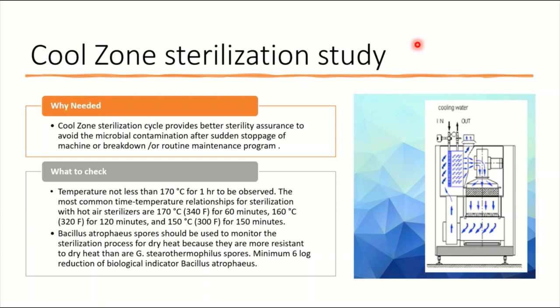This study came out in the last few years, called cool zone sterilization. Here, a couple of temperature combinations: 170 degrees Celsius for one hour to be observed. There are lots of combinations like 160 degrees for 120 minutes, 150 degrees for 150 minutes. Lots of combinations people are trying based on process design and development. The intent is that we need to demonstrate six log reduction by using biological indicator like Bacillus atrophaeus. Bacillus stearothermophilus is not the BI of choice for dry heat. You need to demonstrate six log reduction. That is the expectation of the cool zone. I have an article on cool zone and I will give that link to YouTube description so people can go in detail.